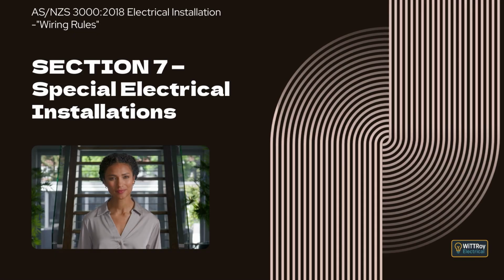Clause 7.2.3.5 Discrimination selectivity of circuit protective devices. This clause explains that protective devices must be selected so that a fault on one safety service does not cause loss of supply to other safety services, and that a fault in the general electrical installation must not interrupt power to safety services. It also explains that fault current limiting devices used to protect safety services must not be used to protect general installation circuits. Finally, it explains that discrimination must be arranged between outgoing circuit protection and upstream protective devices so faults are cleared in the correct order. Clause 7.2.4 Main switches.